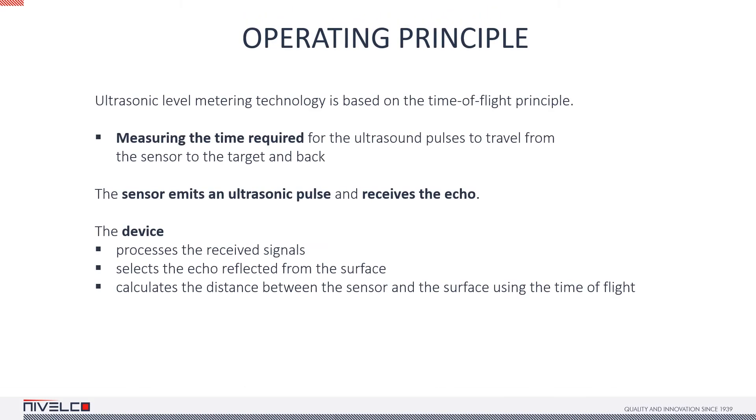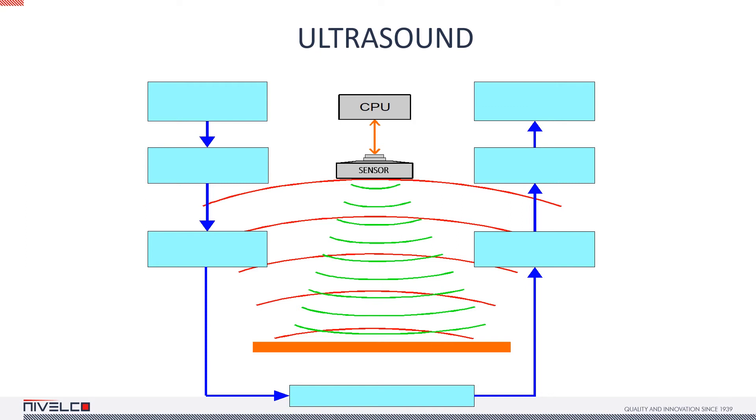Ultrasonic devices use the time of flight operating principle. They measure the time it takes for the ultrasound to travel from the sensor to the measured objects and back. The sensor emits a string of ultrasonic pulses and receives the echoes bouncing back from the target. The device processes the received echoes, selects the ones that carry relevant information and it calculates the distance between the sensor and the measured level.